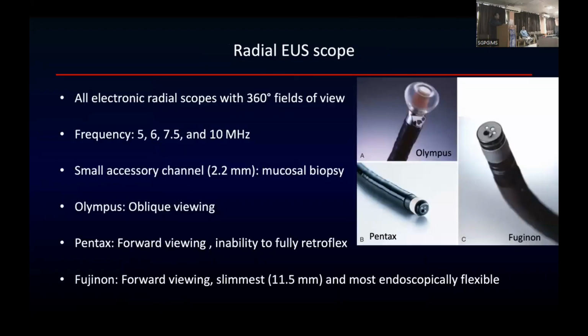So the radial EUS scope, as I mentioned, we don't use it, but you should know the important features. As I mentioned, it has a 360-degree field of view, and the frequency ranges from 5 to 10 megahertz. It has a small working channel of 2.2, with which you can do a mucosal biopsy. There are three major players, as I mentioned: Olympus, Pentax, and Fujinon, and there are some differences in these radial scopes as well. Olympus is oblique viewing, while Pentax and Fujinon are forward viewing. So you may encounter some difficulty during insertion of the scope. However, when you do EUS imaging, it doesn't matter.